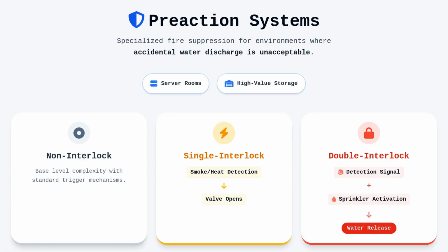This dual requirement design creates a redundant safety barrier that prevents damage from mechanical impact or accidental damage to the sprinkler system. Understanding the logic gates of these systems is crucial because the performance requirements depend entirely on the interaction between the electrical detection circuit and the mechanical valve assembly.